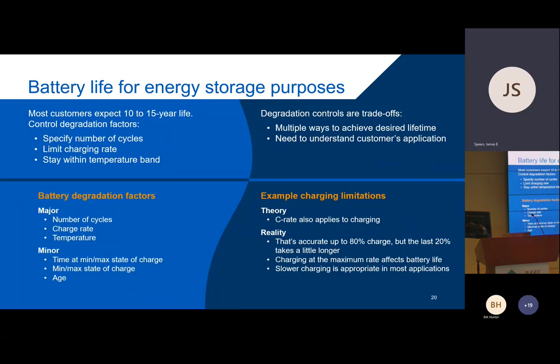It's nice for the batteries to be able to recharge quickly, but the faster I try to recharge them repeatedly, the more negative the impact on service life. You also want to stay within the temperature band. If your ambient temperature is too variable, too hot in the summer, too cold in the winter to be ideal, then you're going to want to have climate control in the battery enclosure or within the battery itself. It can be air cooled and also liquid cooled.